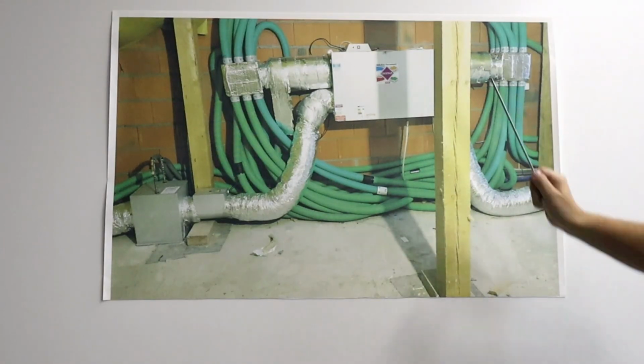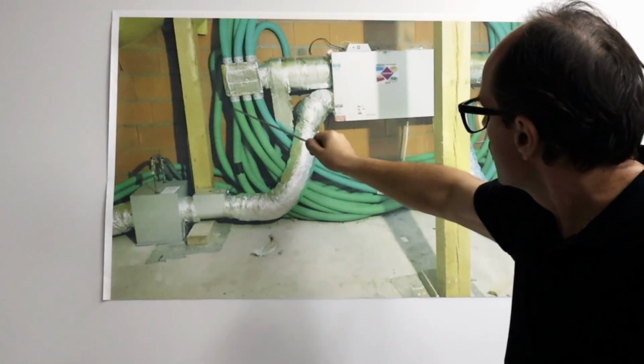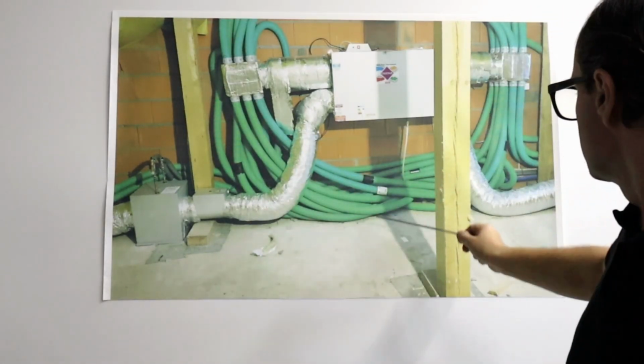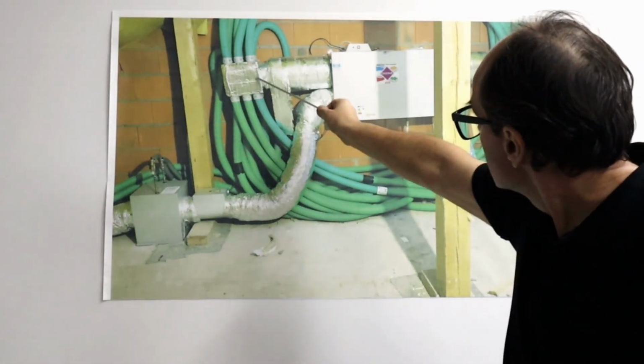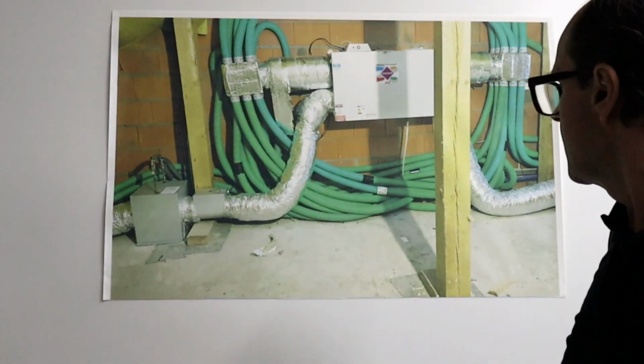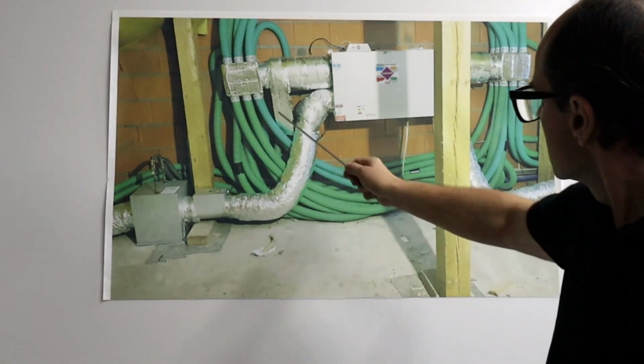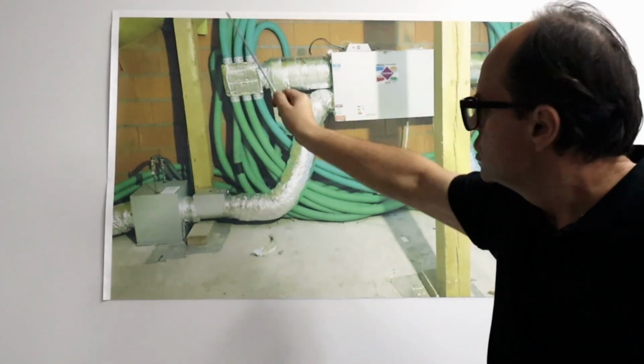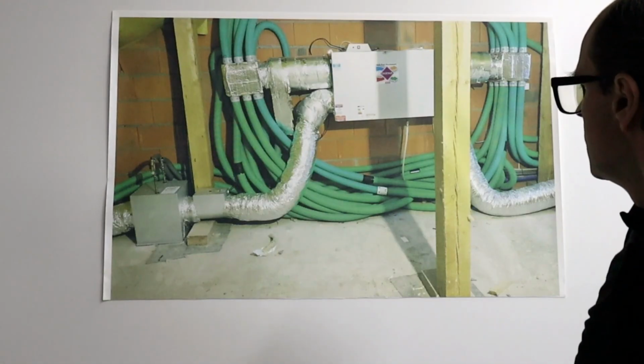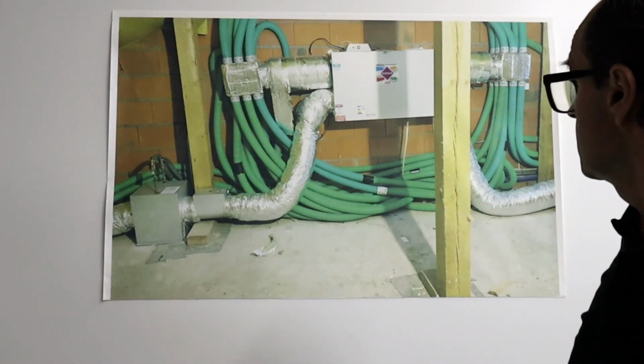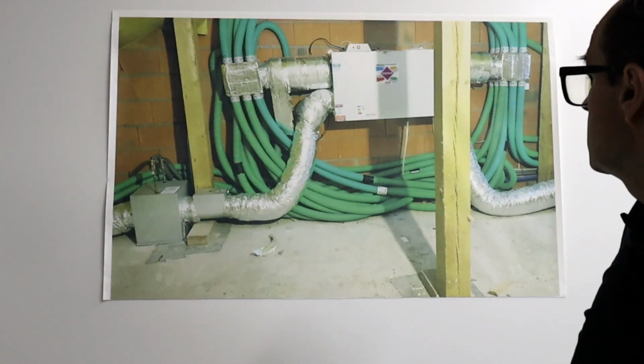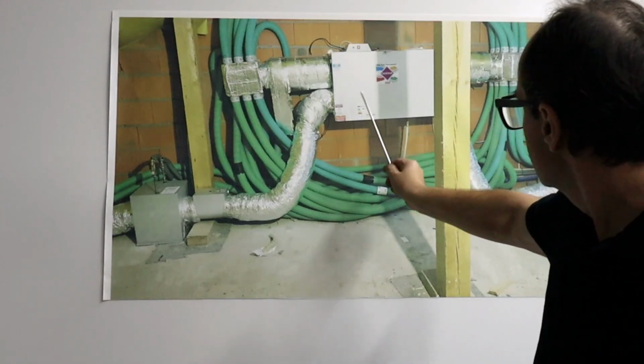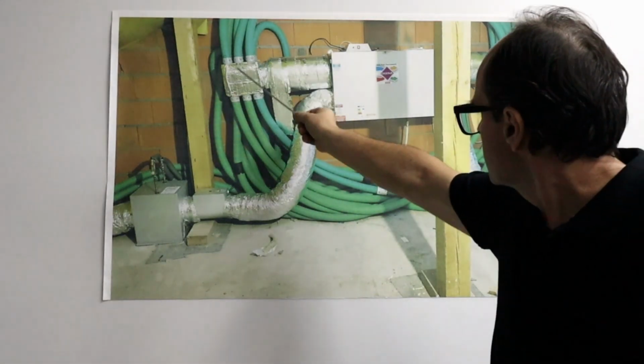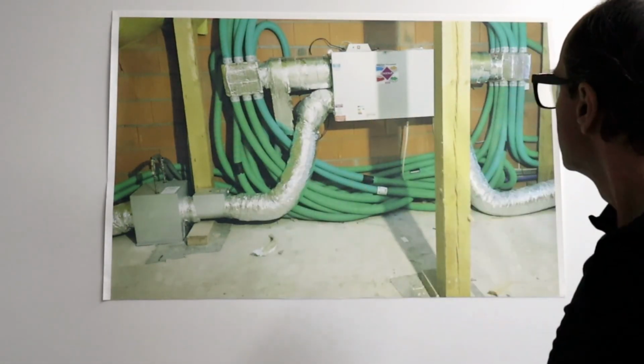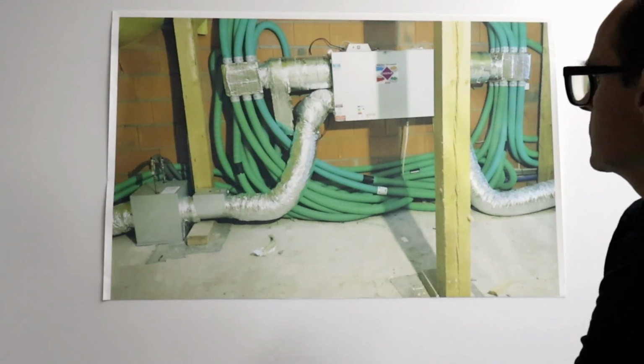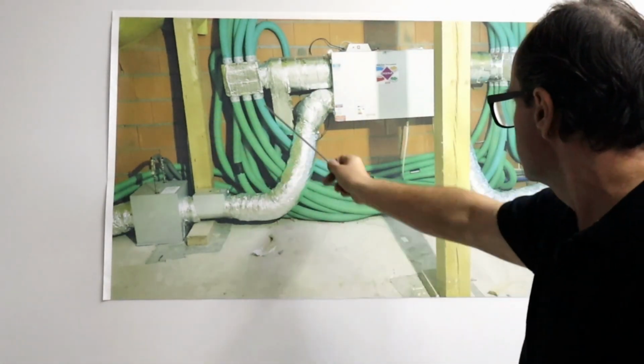Now just take a look. 18 ducts connected to each box. These are ducts with a 75mm diameter. If I'm not mistaken, this is a 2-story house, so the connections from this box extend to the ground floor and to the attic. Let's say it's 35 meters per duct, 35 cubic meters per hour multiplied by 18. That's about 630, but I don't know if this is a 600 or 450 unit. For it to push all this air through both in this direction and that one, it would have to be at least an 800, and then it would compensate for these bent fittings.